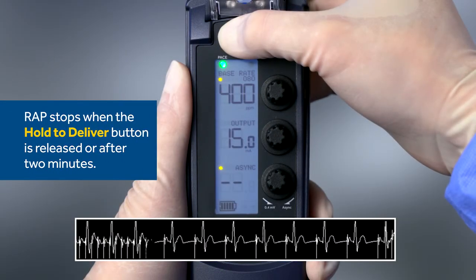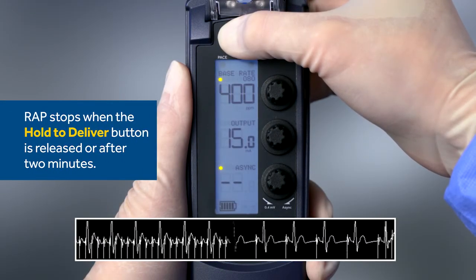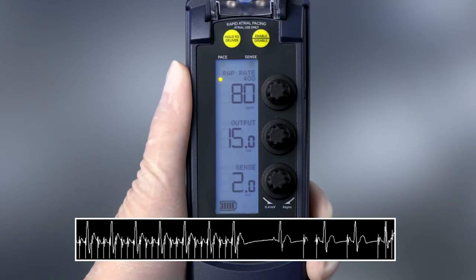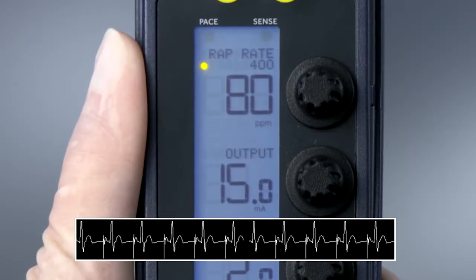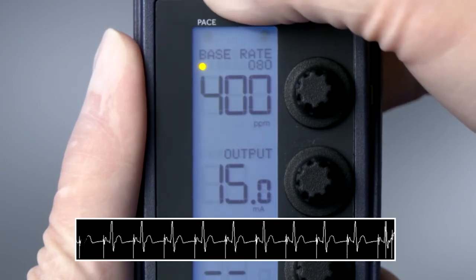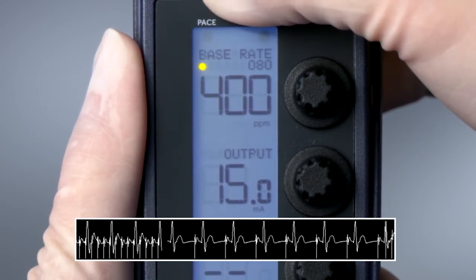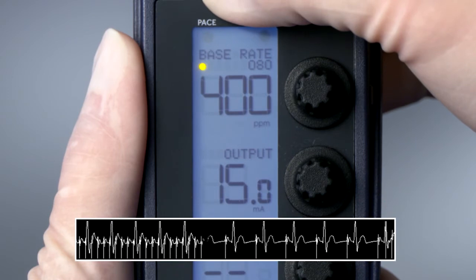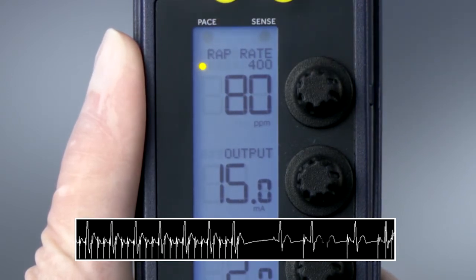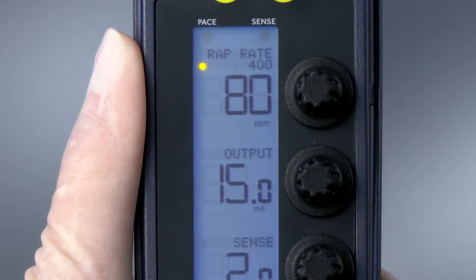RAP delivery stops when the Hold to Deliver button is released. The temporary pacemaker stops delivering Rapid Atrial Pacing and resumes operation at the non-RAP settings within 3 seconds. Notice that since the output was adjusted during Rapid Atrial Pacing, the new setting is retained when RAP is terminated.